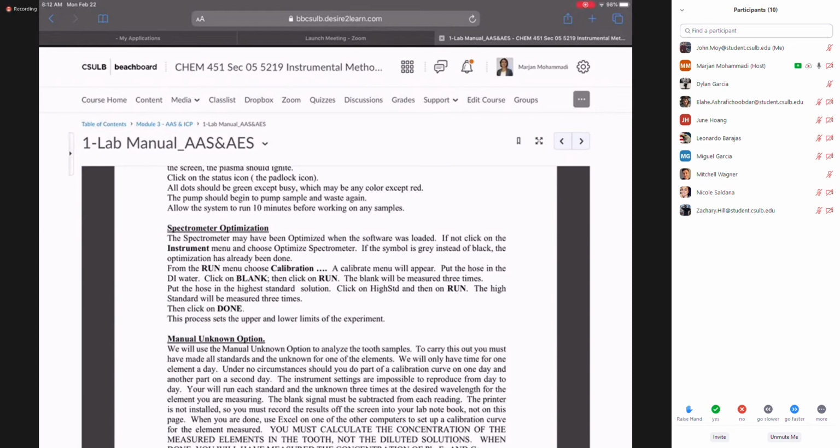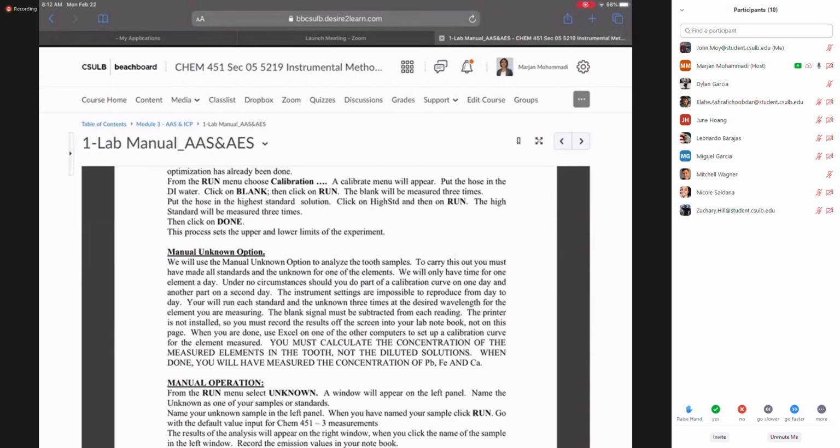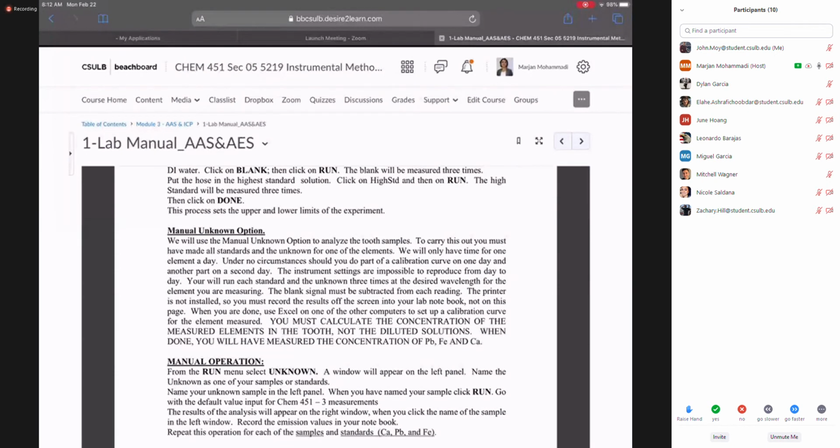And then after 10 minutes, when we have the plasma stable, we had to do the calibration. Calibration is happening right here with the 0, that is blank water, pure water, and 100 ppm, that's the highest concentration. So for each sample. The good part about the ICP is that it's running and measuring all 3 elements at the same time.